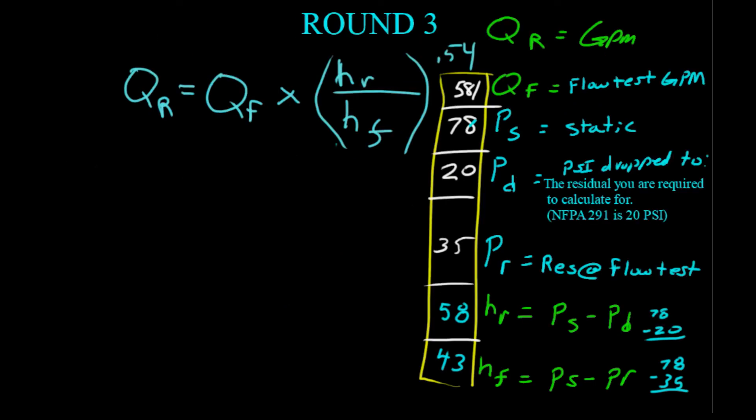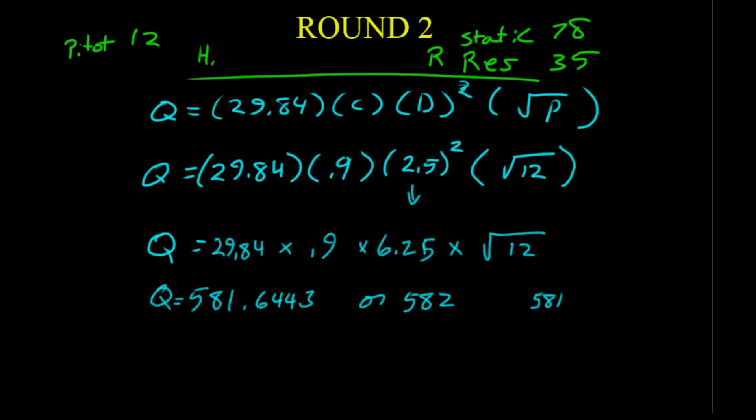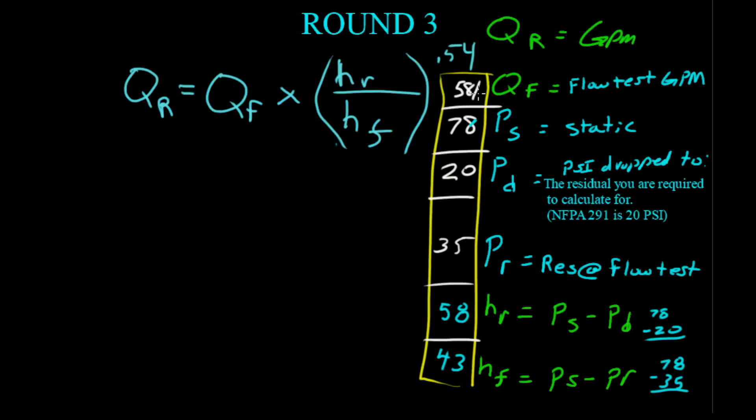Round three. We're going to take the results from this. We'll put 581 in here. And we're going to work out this equation. So, the HR. So, PS minus PD will be 78 minus 20. It will be 58. HF up here. PS minus PR. 78 minus 35 gives you 43. So, the H sub F is 43.